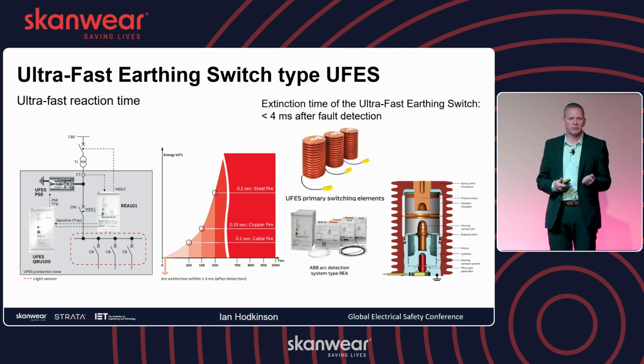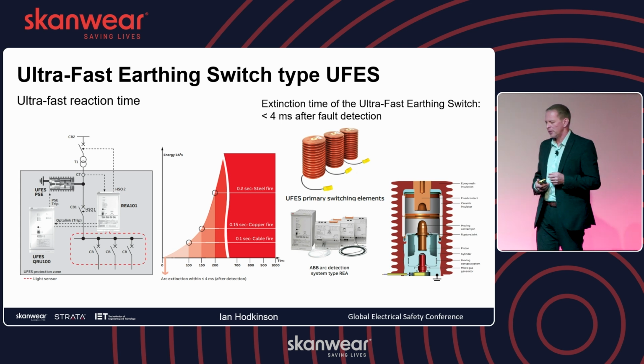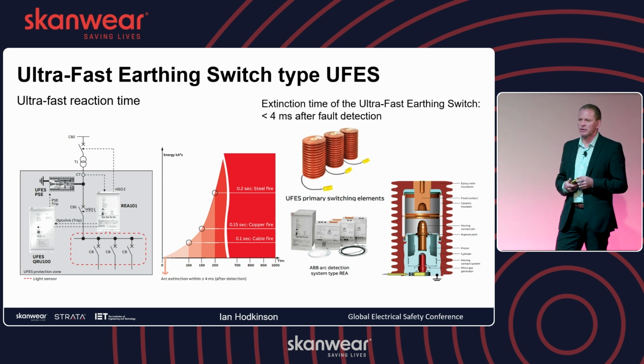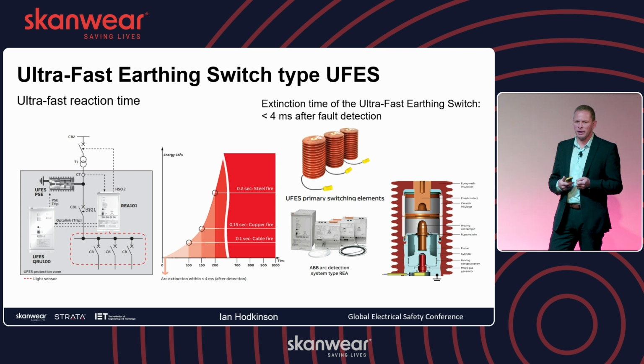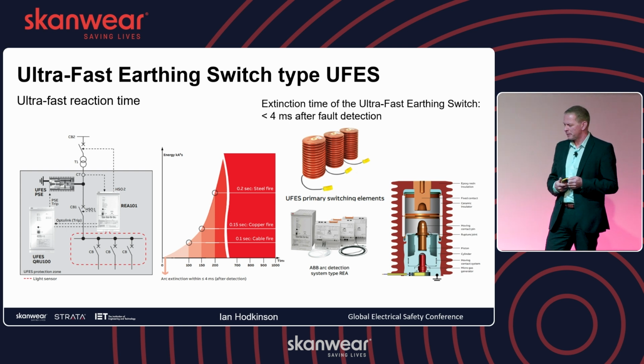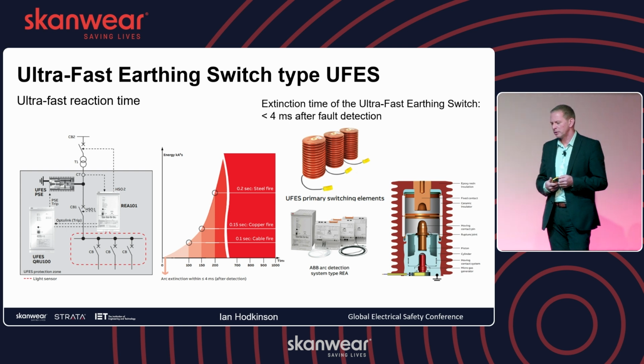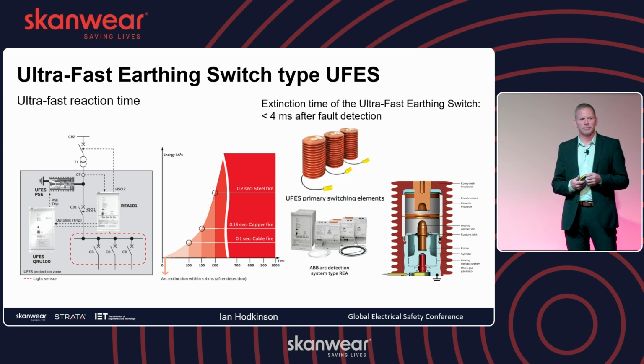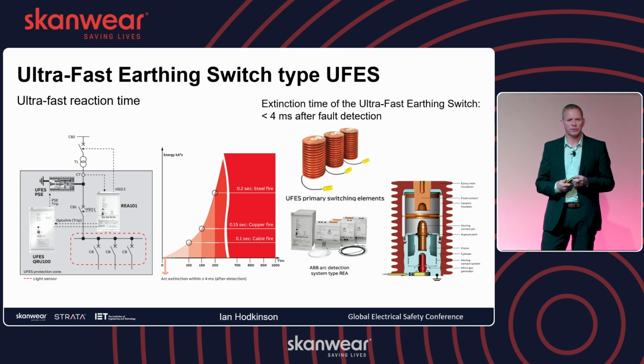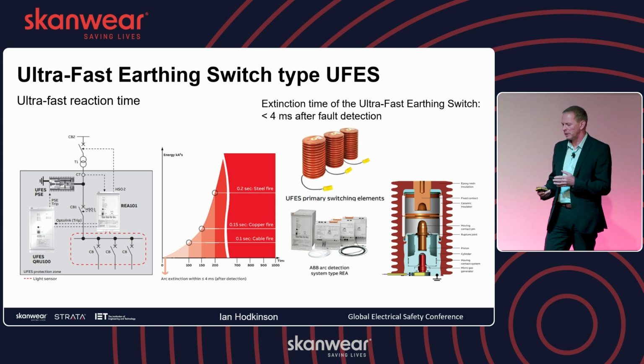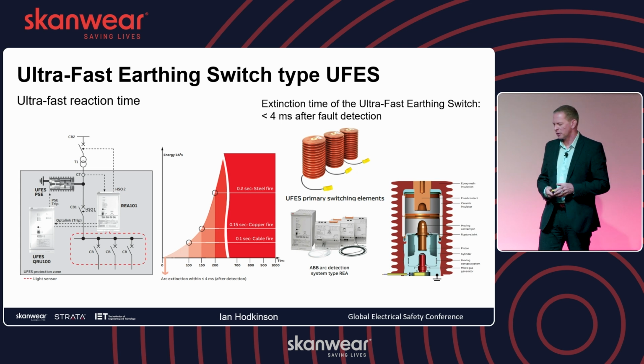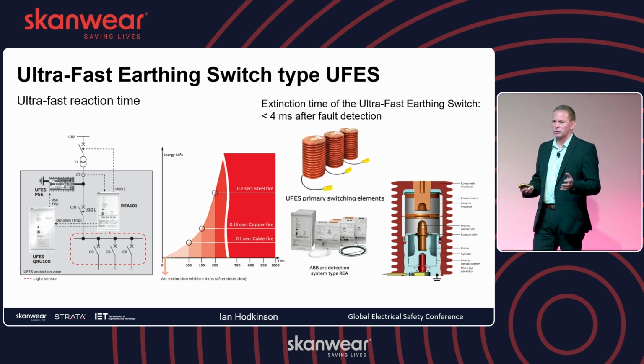So it takes 1 or 2 milliseconds to detect it, and this is where it sends a signal to the UFES. It acts very quickly, like airbag technology, shoots the rod up and makes the connection, taking the full energy of the arc down to earth, clearing it in another 2 milliseconds. So a full 4 millisecond clearance time, and then your breaker can do its trip in its own due diligence time. But that's just to isolate the system.